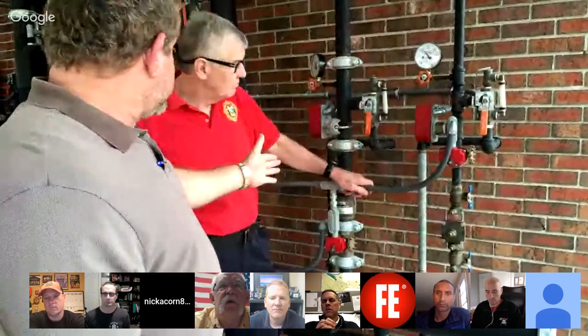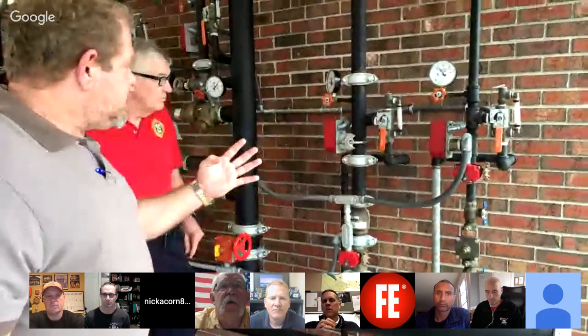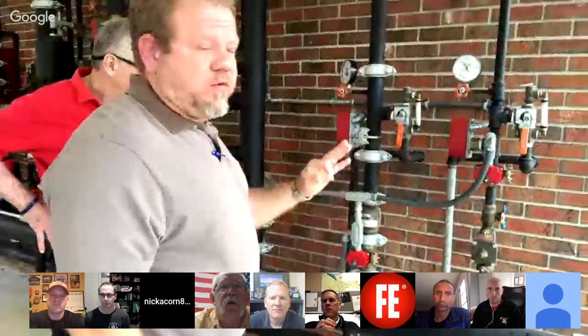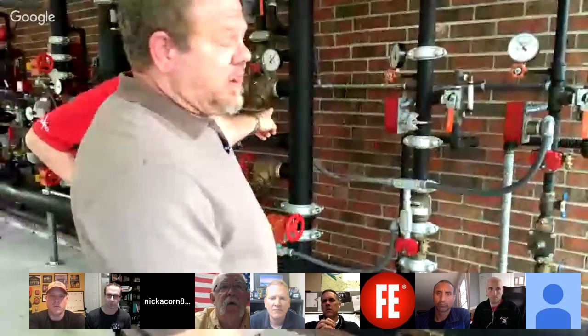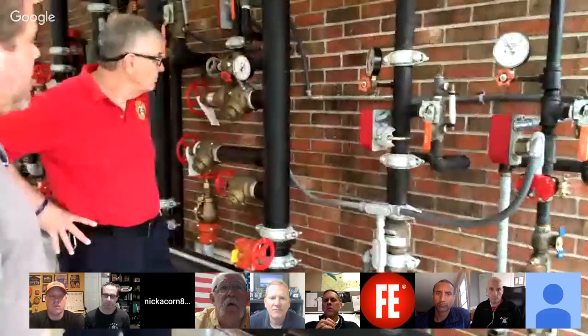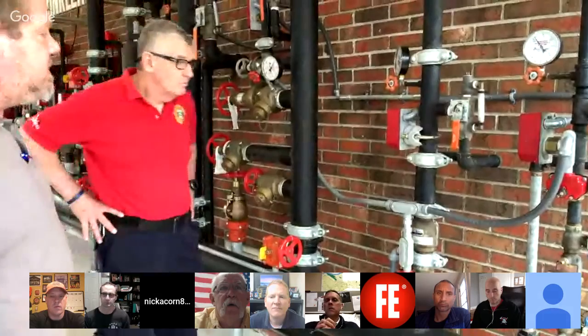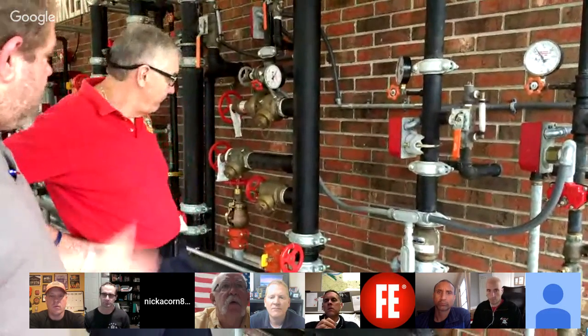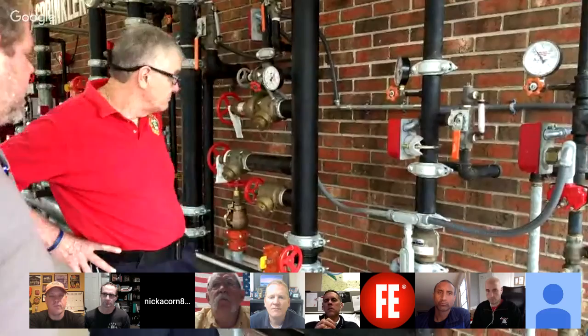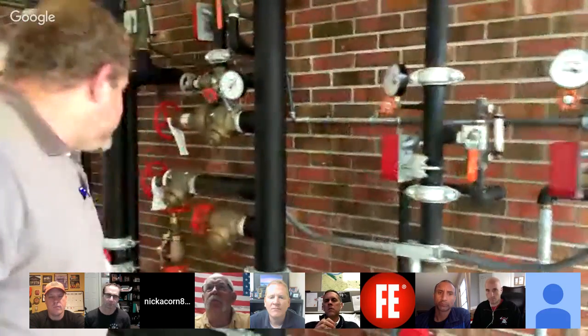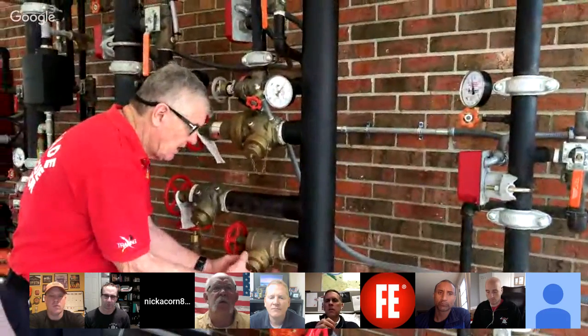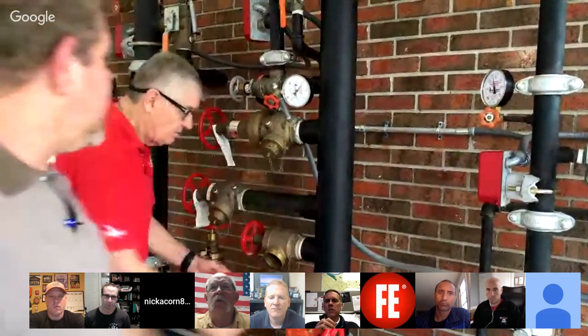We'd move to the next, which is our multi-family, up to 4 stories in height, 13R. And once we go over 3 levels in Florida, or 30 feet to the highest occupied floor landing, we've got to have a standpipe. So the correlation between the standpipe and the 13R riser is on purpose. In our standpipe application, we've got a standard weight fire hose valve. This is just a conventional, factory set. And then we have a field adjustable PRV. And then we would have a floor control valve assembly like we would in a multi-level building.